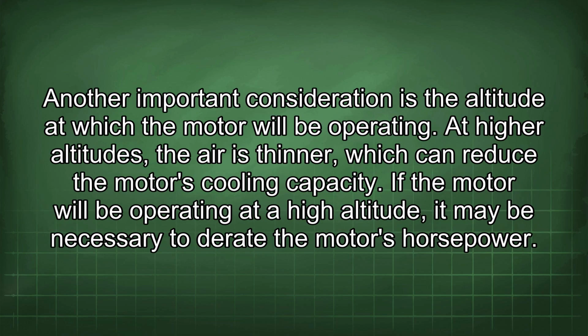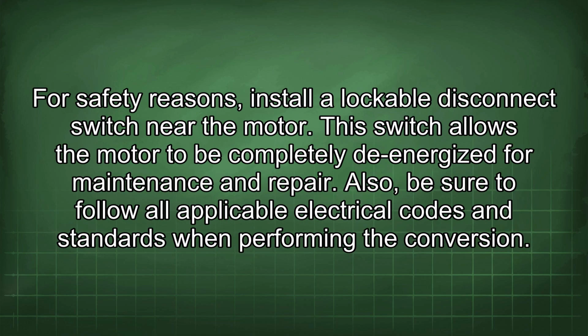Another important consideration is the altitude at which the motor will be operating. At higher altitudes, the air is thinner, which can reduce the motor's cooling capacity. If the motor will be operating at a high altitude, it may be necessary to derate the motor's horsepower. For safety reasons, install a lockable disconnect switch near the motor. This switch allows the motor to be completely de-energized for maintenance and repair.